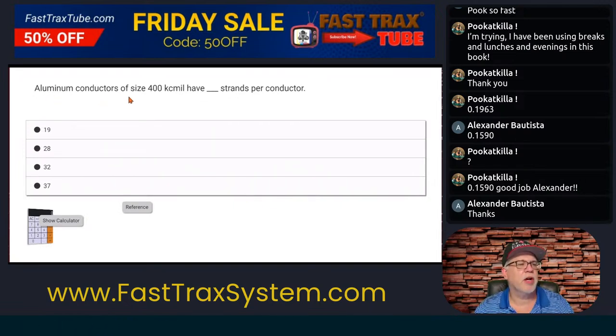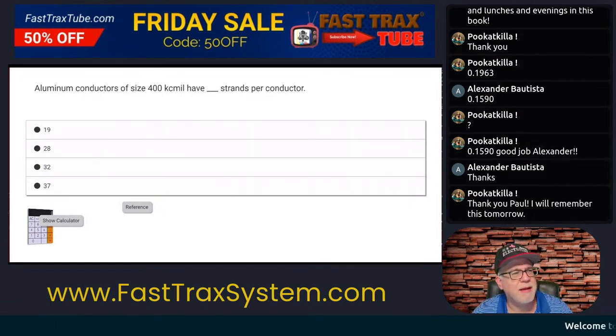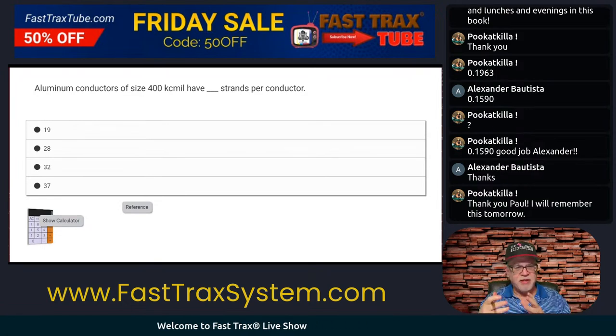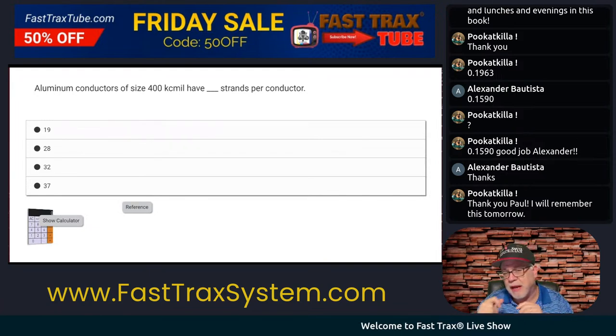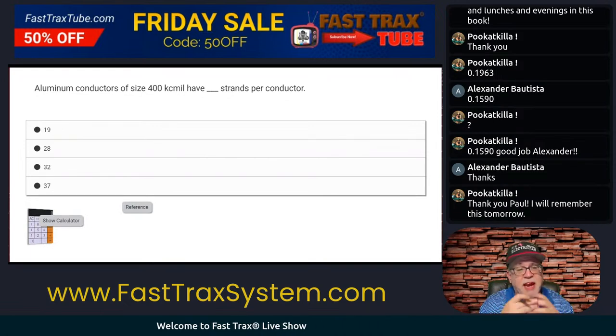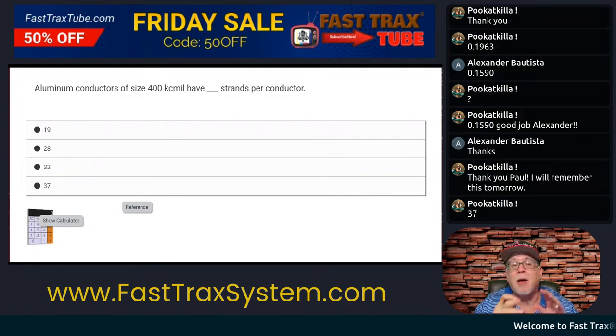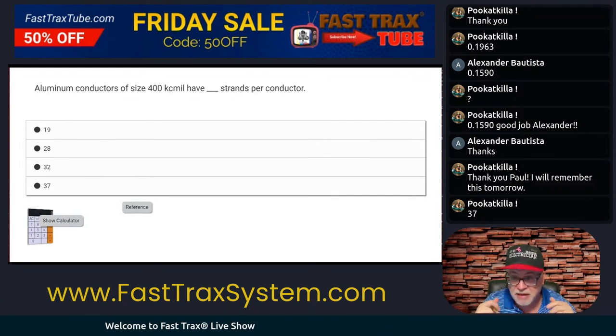Aluminum conductors of size 400 kcmil have blank strands per conductor. How many strands per conductor? We're talking stranded. Remember earlier I said a table to keep in mind was the actual properties of a conductor. Actual properties of the conductor are going to be Chapter 9, Table 8. Chapter 9, Table 4 for raceways and percentage of fill. Chapter 9, Table 5 for conductor properties when it comes to the area. Chapter 9, Table 5A for compact. Chapter 9, Table 8 for stranding questions.